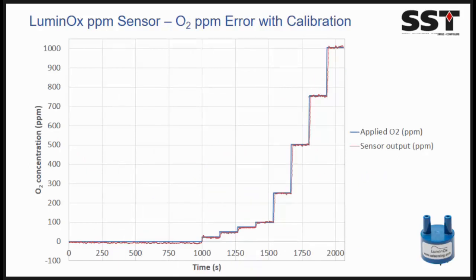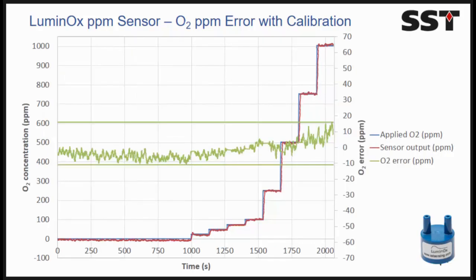What this shows, so this is what we call a verification. So we get all the values at 20 degrees Celsius over the full range. In this case, we're going to 1000 ppm because that's what we're trying to do. So the blue here is the applied oxygen concentration that we see from our gas blending system. Then we put the sensors through the calibration process, so going from -30 to 60 Celsius, from 0 to 1000 ppm. Then what we do is we record the sensor output in ppm from what we've seen from the calibration. So we compare the data before calibration to what we compared after. And what this did was give us a nice error of plus or minus 15 ppm in this case. So this is the absolute error of the sensor over the full calibration range.